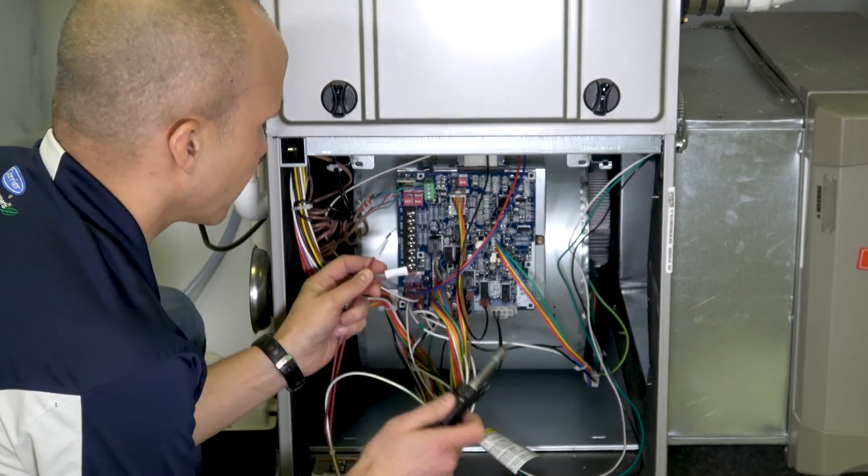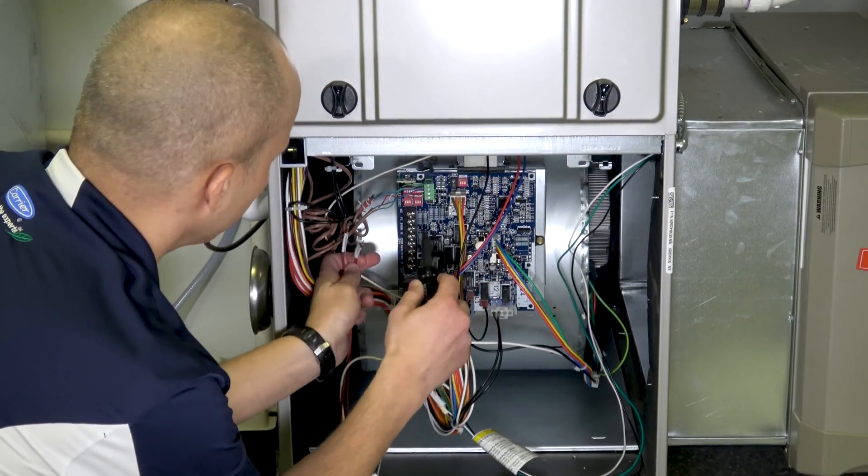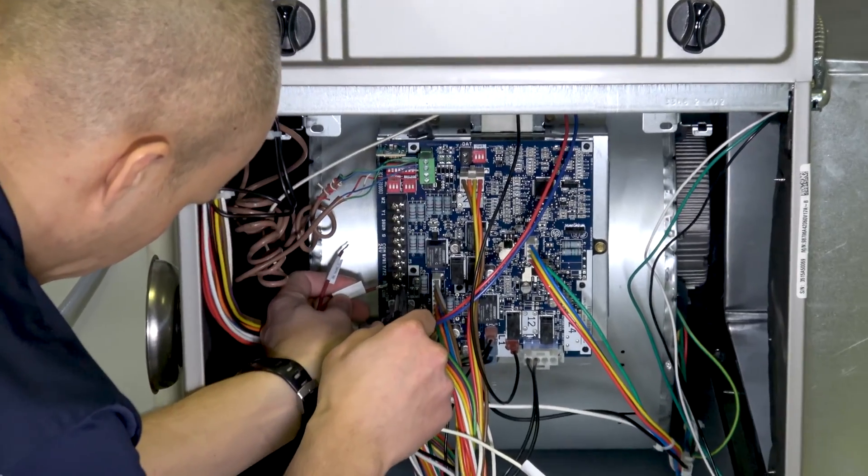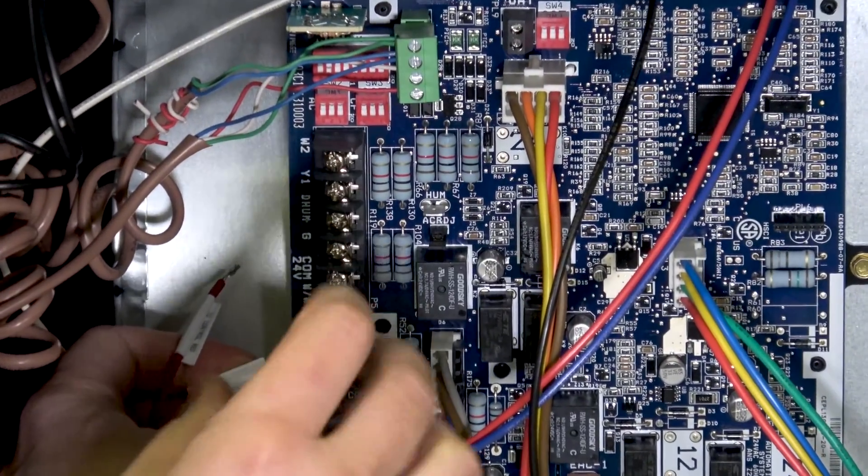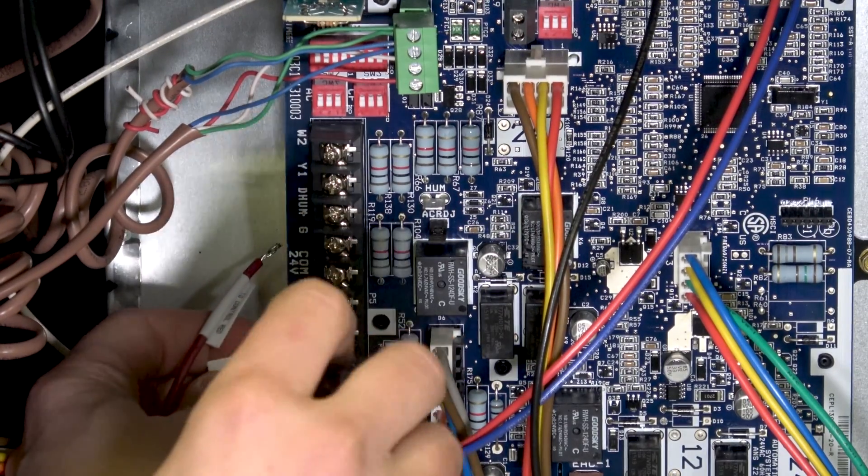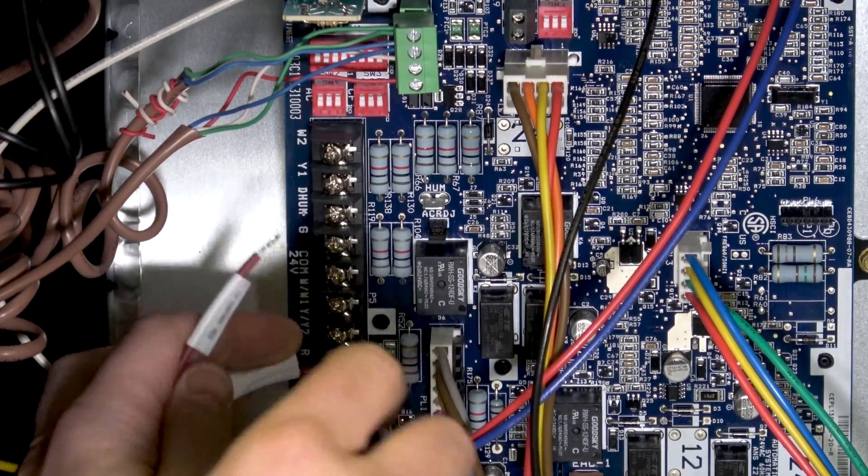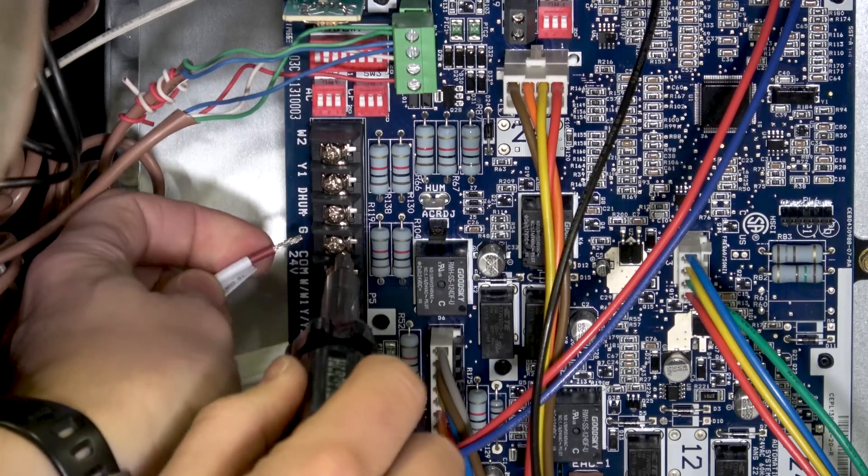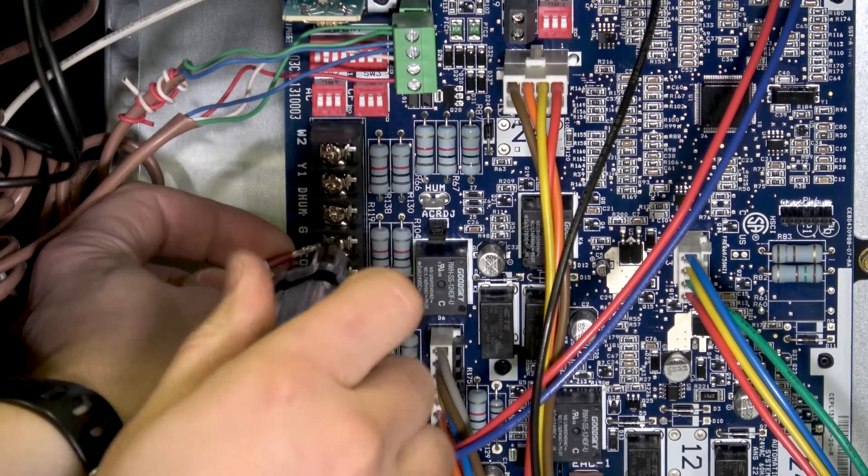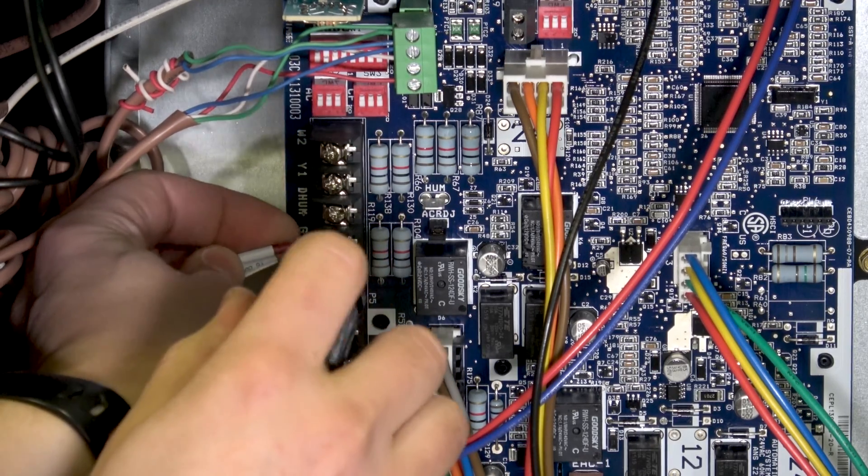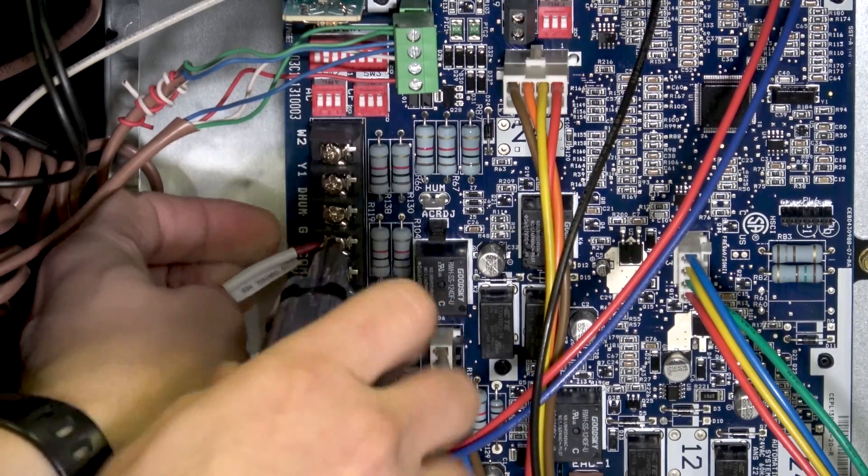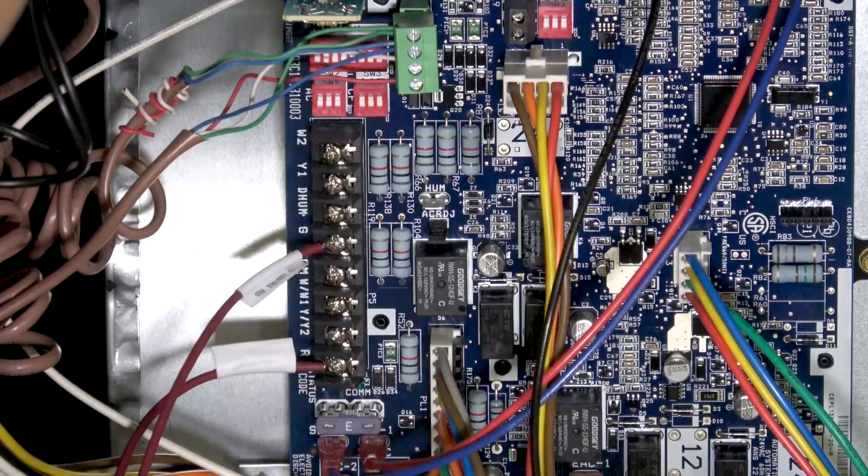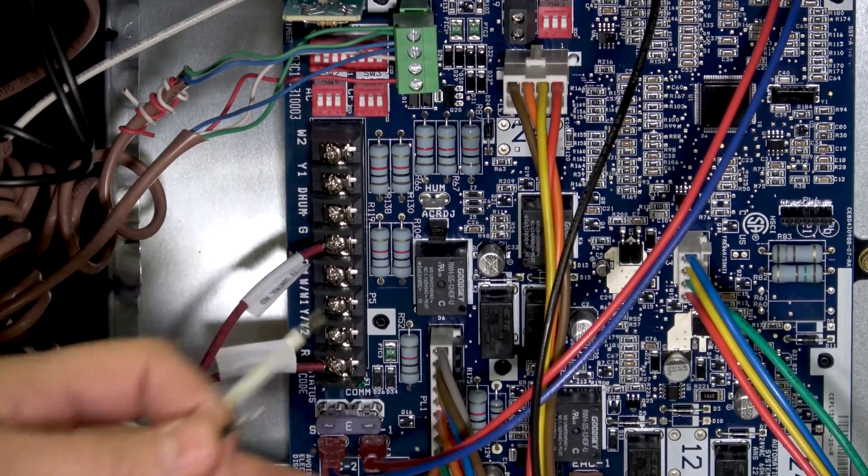Down here at the furnace we're going to take our two red contact wires and we are going to terminate them on R and onto G. That's no longer a fan signal on this particular application with these thermostats. That is a miscellaneous input. That's R and G.